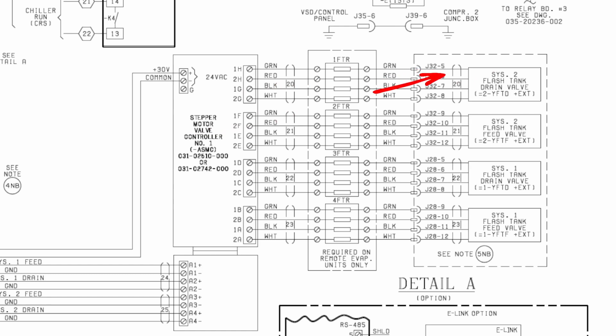This being a 4-wire, you can see we have a green, red, black, and white. These are your coils here. In a 5-wire setup, we would have a 5th wire, and that 5th wire is actually a common wire. With this 4-wire setup, red and green is one coil, and black and white is a second coil, or second part of your stator. So your stator is split. These are stepper motors.